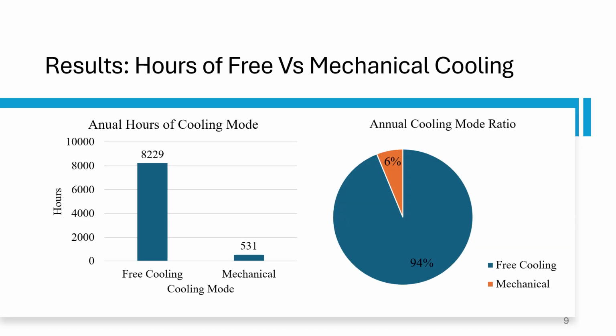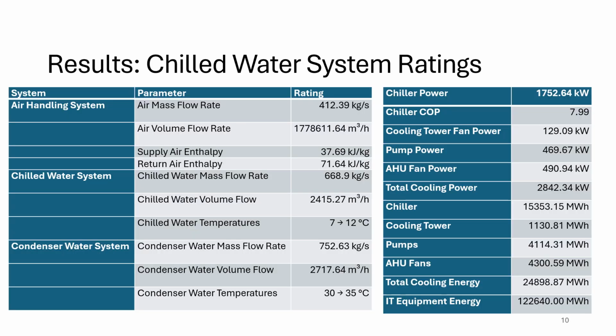To further explain the frequency within the year where each mode of cooling will be used, the graph on the left shows that free cooling will be used for 8,229 hours within the year, whereas mechanical cooling will be used for 531 hours during the year. The graph on the right shows that free cooling will be used for 94% of the time during the year and mechanical cooling 6% of the time. These tables show the designed chilled water system ratings. The table on the left shows the flow rate of water and air and their temperatures that provide cooling for the data center. The table on the right shows the power ratings of the various components of the system.